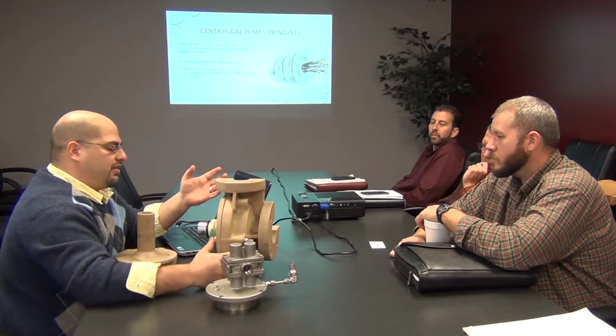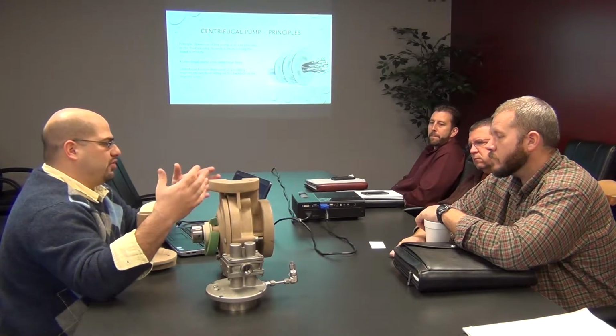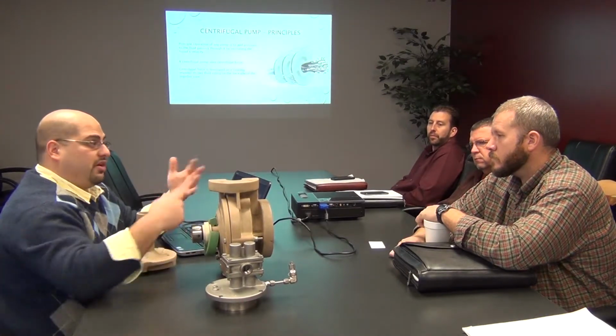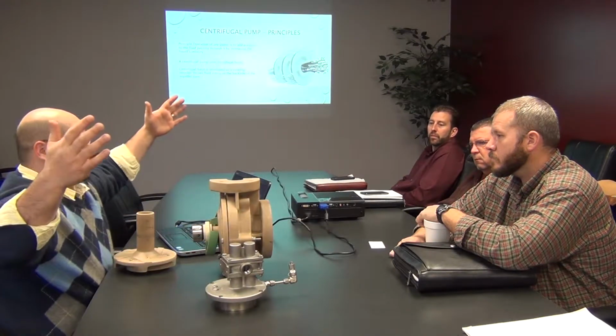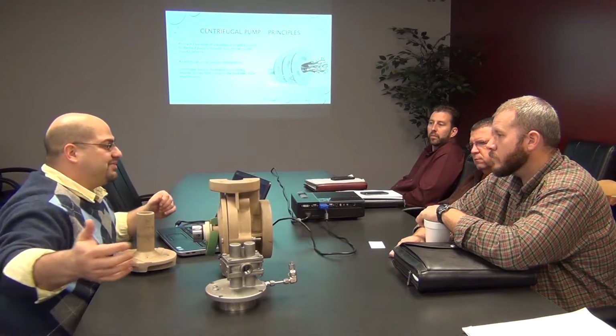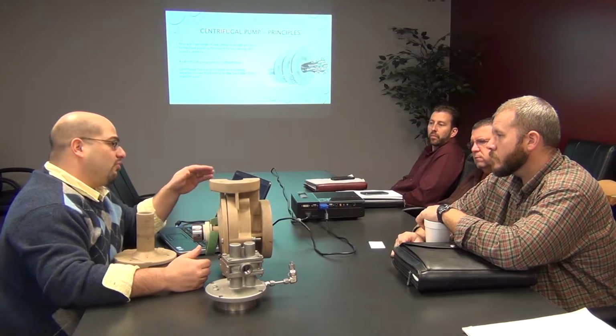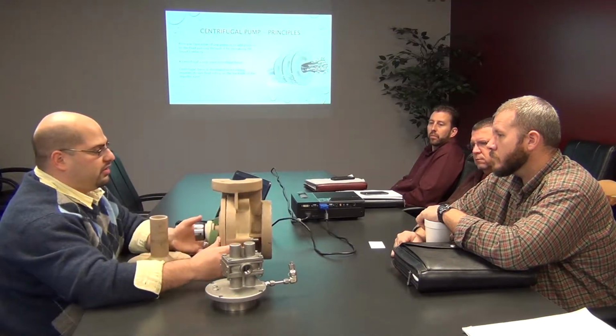Now, based on the size of your impeller, your suction and discharge, which is known as the affinity laws calculations, you can calculate the size of your suction, discharge, impeller, and your speed, and figure out how much flow or how much pressure you can generate. So you could increase to an 18-inch impeller and be able to drive that much more pressure. Or they do other things like stages. A pump could have multiple impellers, so your flow remains the same, but you're able to develop a higher rate of pressure. We'll go into some of that.